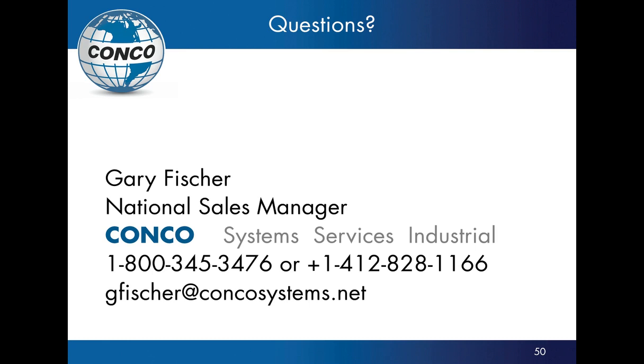Okay, next question. Would you be able to differentiate among cracking, pitting, under deposit corrosion, etc. via eddy current testing? Yes, you should. If you do the eddy current test and you use the multiple frequencies, an experienced level 3, which you should have, or a level 2A, should be able to take a look at the data and see whether you have a crack or whether it's a pit. Under deposit corrosion will come out once you have it removed.